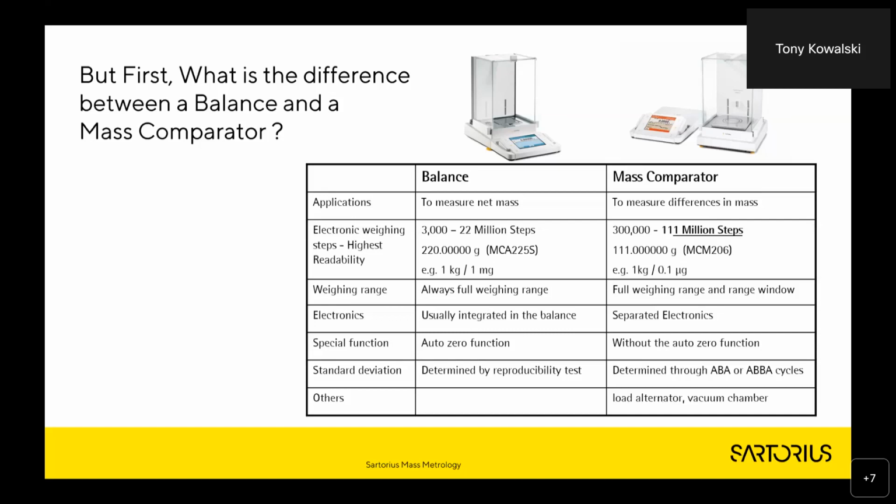Also, on a laboratory balance, there is something known as auto zero or zero tracking. It's a little feature that makes your balance look quite nice. When it's being tared to zero and sitting on the bench, it may want to drift a little bit up or down as the temperature in the lab is changing, but this auto zero function just keeps the balance at zero. It's like this little guy inside who is pressing the tare key.